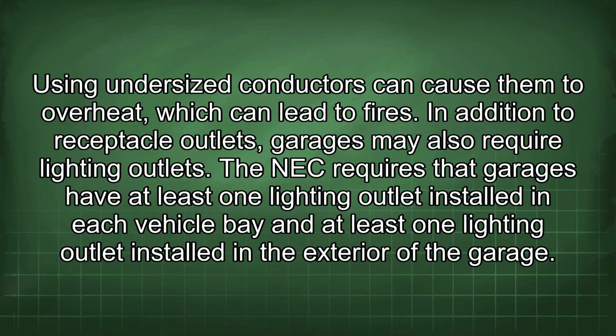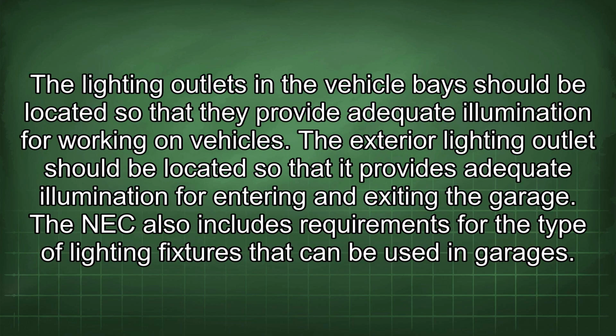In addition to receptacle outlets, garages may also require lighting outlets. The NEC requires that garages have at least one lighting outlet installed in each vehicle bay and at least one lighting outlet installed in the exterior of the garage. The lighting outlets in the vehicle bays should be located so that they provide adequate illumination for working on vehicles. The exterior lighting outlet should be located so that it provides adequate illumination for entering and exiting the garage.